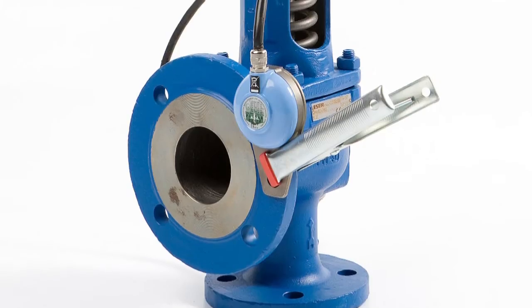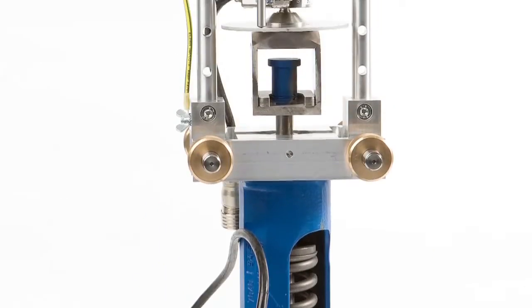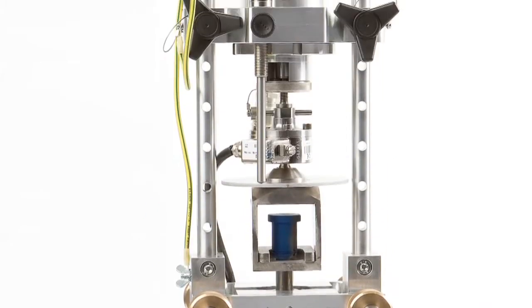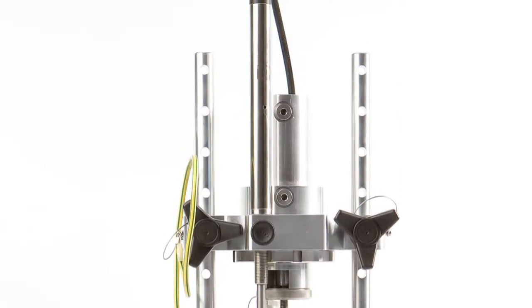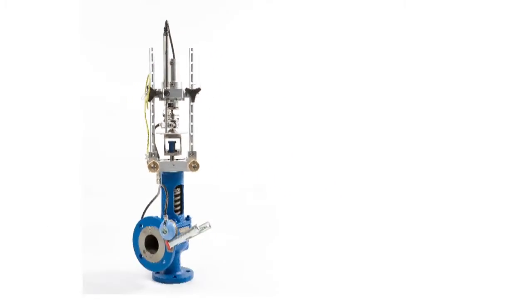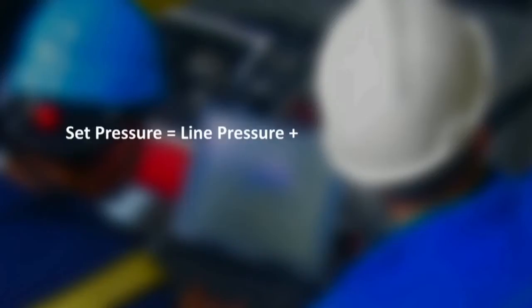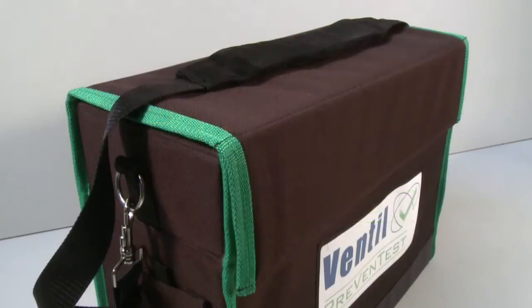The cracking point is the set pressure of the valve — the moment the disc commences to lift. This point is detected by the lift, acoustic and force sensors, and the corresponding measuring values are used in the automatic set pressure calculation. Set pressure equals line pressure plus pulling force over valve seat area. The Ventil Preventest system is available in three versions.